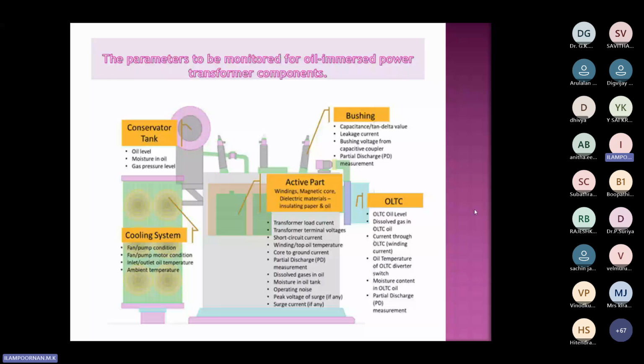What do you mean by high voltage lines? The bus bars, whatever it may be, a high voltage line or a bus bar. It may be on either side, in the substation or in the generating station, so power transformers are used on both sides. So what is the necessity of the bushing, I'm asking? You are telling about the end connection of the bushing. I'm asking why the bushing is there in between the line and the transformer.